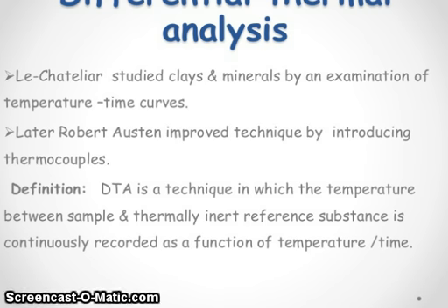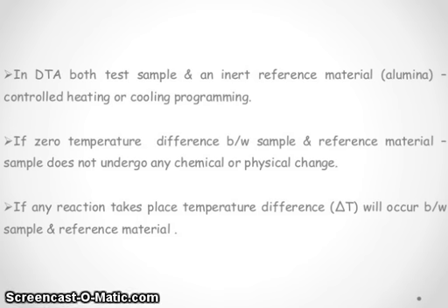So, what are the definitions? DTA is a technique in which the temperature difference between sample and thermally inert reference substance is continuously recorded as a function of temperature or time.